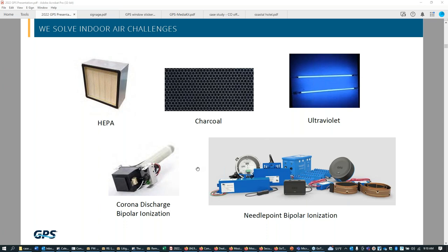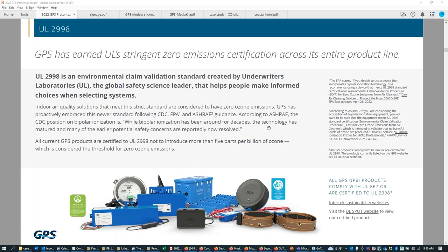And one of the ways that you can distinguish between the OEMs that offer this technology is looking for an Underwriters Laboratories credential that addresses the potential for ozone generation. So UL has two different certifications that OEMs can apply for and achieve. The lower certification is UL 867, and this is the credential that California accepts, and that is a cap of 50 parts per billion of ozone generation right near the generation of the ions. The more strict credential is called UL 2998, and that sets a cap for devices at 5 parts per billion of ozone generation. And just to give you a frame of reference, the typical laser printer or copy machine tends to generate more than 5 parts per billion.